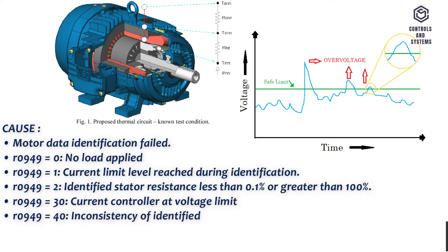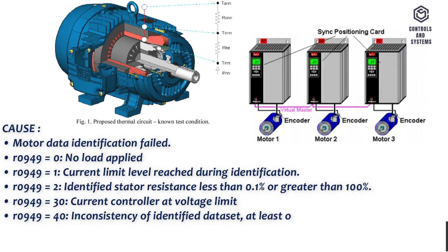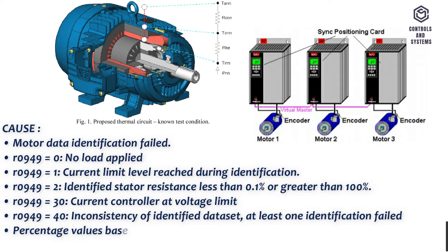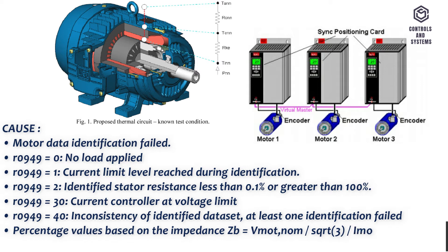R0949 equals 2: identified stator resistance less than 0.1% or greater than 100%. R0949 equals 30: current controller at voltage limit. R0949 equals 40: inconsistency of identified data set, at least one identification failed. Percentage values based on the impedance ZB equals VMOT(NOM) divided by SQRT3 times IMOT(NOM).